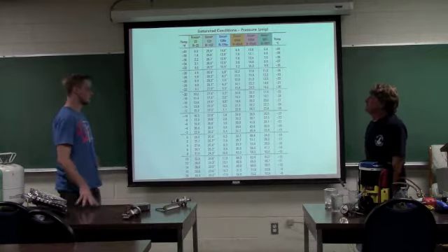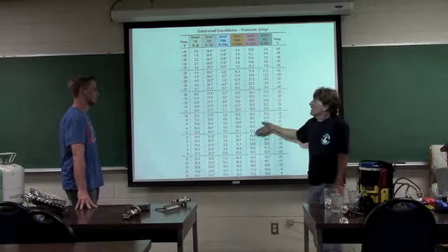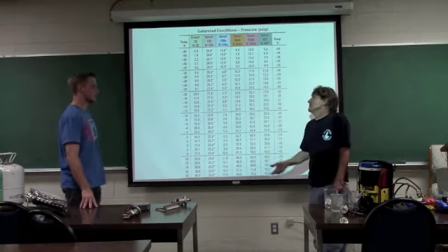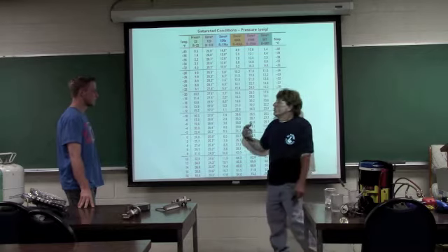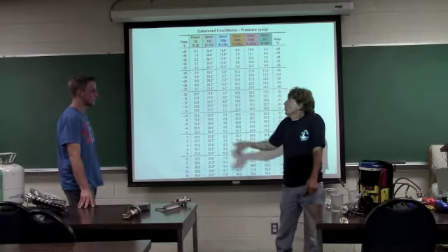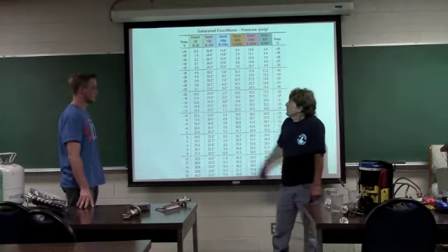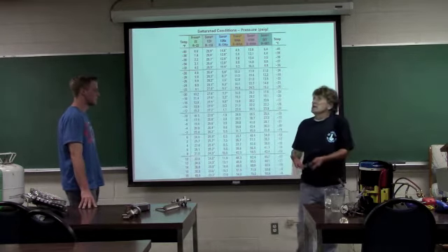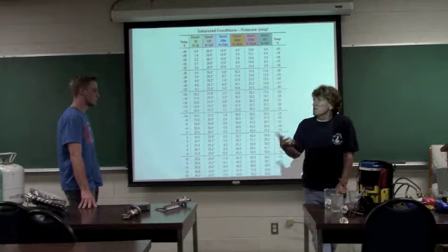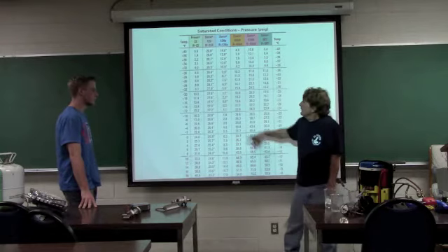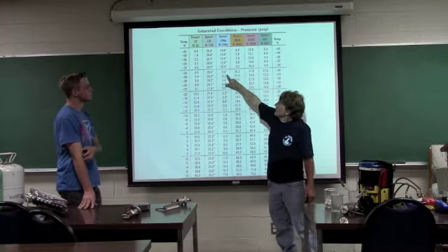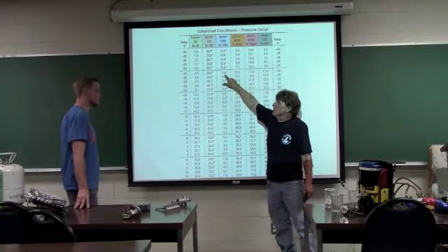That's a little bit different. Oh, it is. The temperatures, this relationship is still the same though, right? Of course, yes. So we're going to lower temperatures. Exactly. So let's say normally I want the refrigerant colder than the space temperature, right? Correct. So if I wanted 10 degrees space temperature, and let's say my evaporator is designed to be a 20 degree delta T difference between the refrigerant and the ambient, I would subtract 20, which would make this negative 30. So if I had 134A, the pressure would be 28 inches in vacuum.